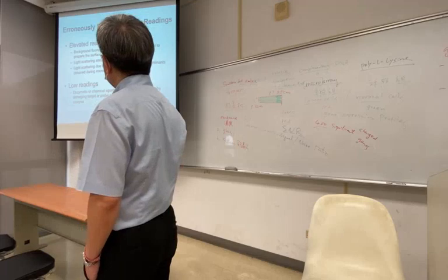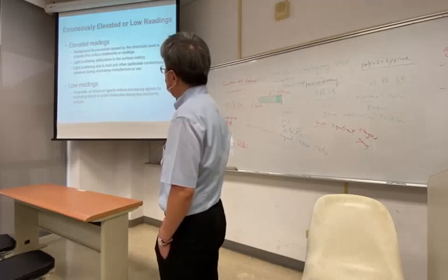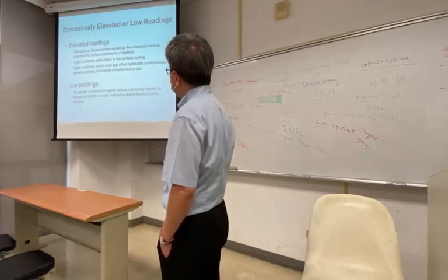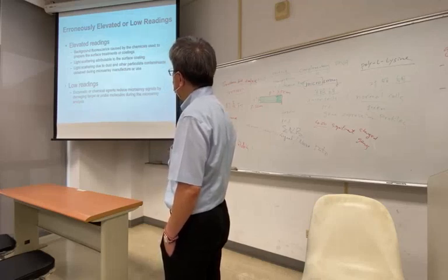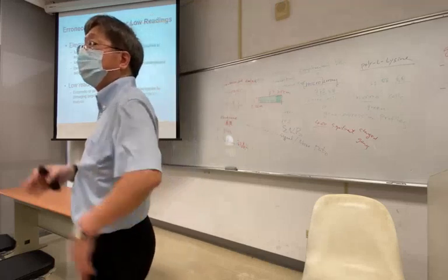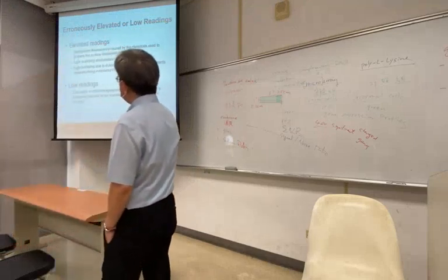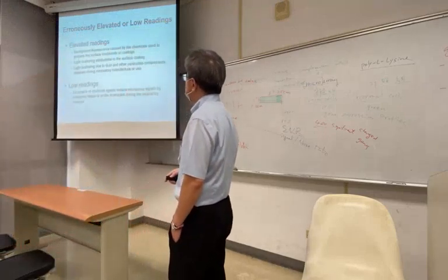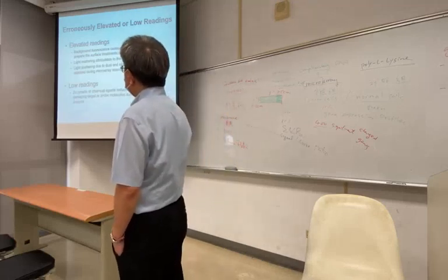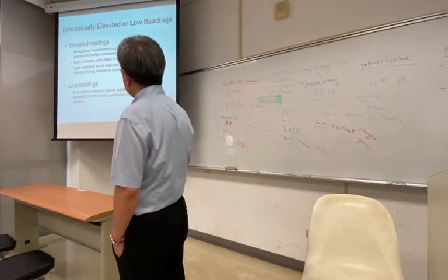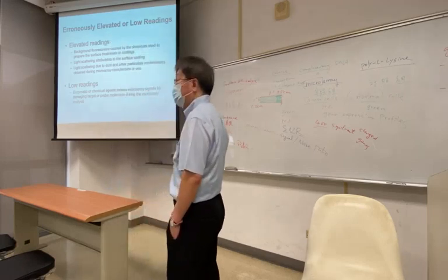So for either elevated or low readings, I already told you, there is background fluorescence caused by the chemical used to prepare the surface treatment or coating. So that's a no-no, right? You don't want to use something that will increase your background fluorescence. And of course, light scattering. I already told you, dust or other contaminants, maybe during the microarray manufacture or use.